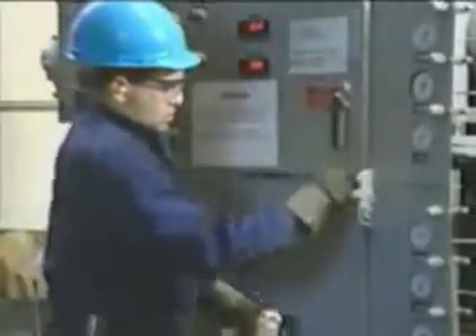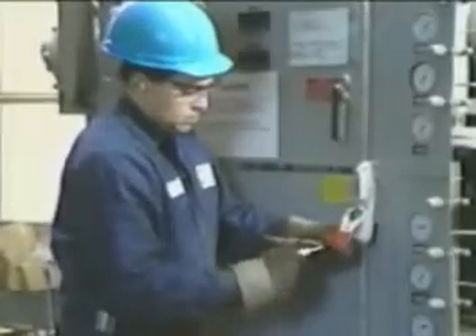Whenever you are performing service or maintenance on any machine where unexpected startup or release of stored energy could cause injury, you must perform lockout tagout procedures. Service or maintenance activities include constructing, installing, inspecting, or modifying equipment. For example, you should lockout tagout when repairing electrical circuits, cleaning or lubricating machinery with moving parts, or clearing jammed machinery, even changing light ballasts. During normal operating activities, you will not need to lockout tagout. However, if you must remove or bypass a guard or other safety device, or if you must place any part of your body where you could be caught or trapped by moving machinery, you must lockout tagout.